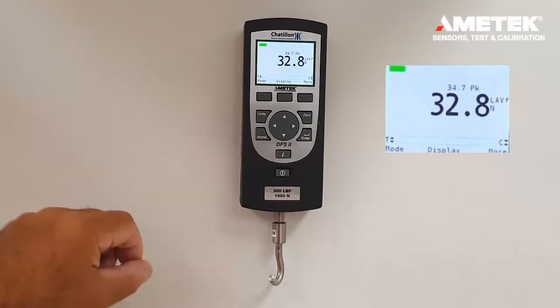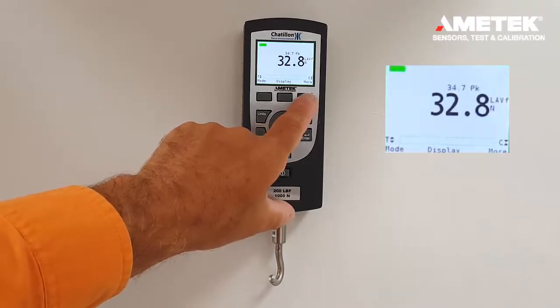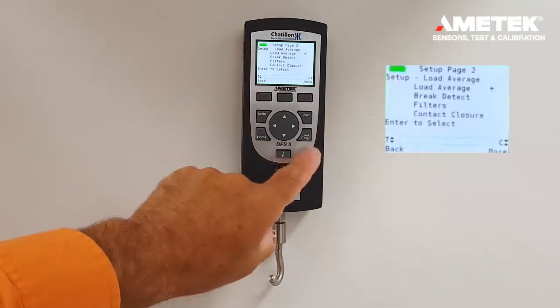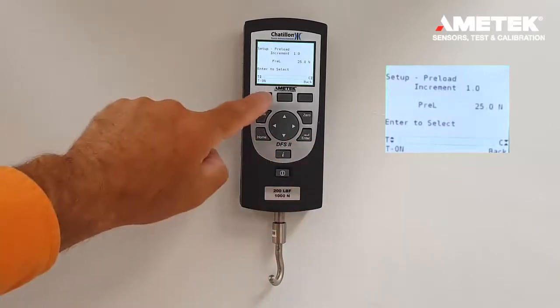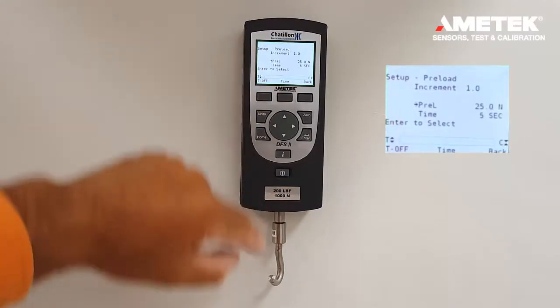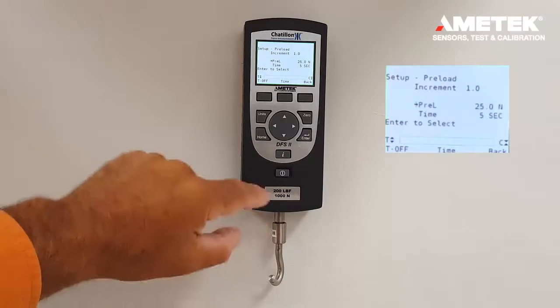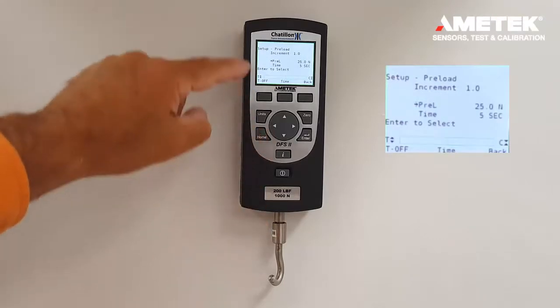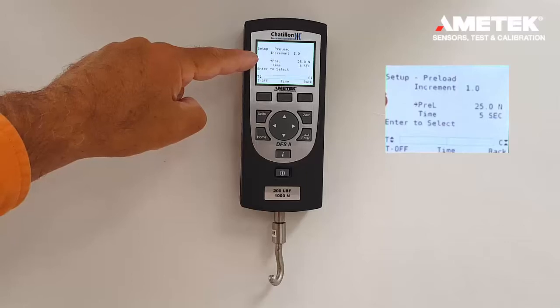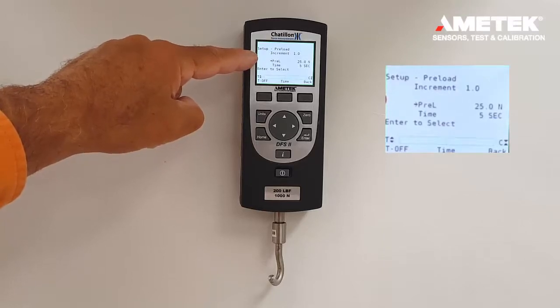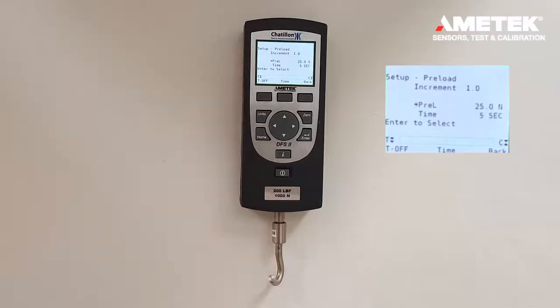Now let's do a test using the time lapse. Press the mode button three times again, enter the load averaging menu, and press enter. We have the time set at five seconds and the preload at 25 newtons. As soon as we reach a preload of 25, the gauge will start counting until it reaches five seconds and end the averaging calculation. However, if the load drops below 25 newtons before the time is reached, the test will end early.